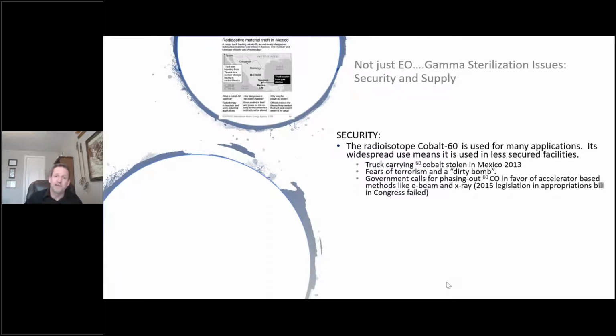So gamma also has some issues. Not as critical as the ethylene oxide issues, but the two biggest issues with gamma sterilization are security and supply. There's an interesting article you can Google. There was a truck that was carrying radioactive cobalt. With gamma, they take cobalt 59, put it into a nuclear reactor, and it sits in there for 2 years, and then it comes out as cobalt 60, which is radioactive. That's what's used for the gamma knife procedure for cancer treatments, and for medical device sterilization.